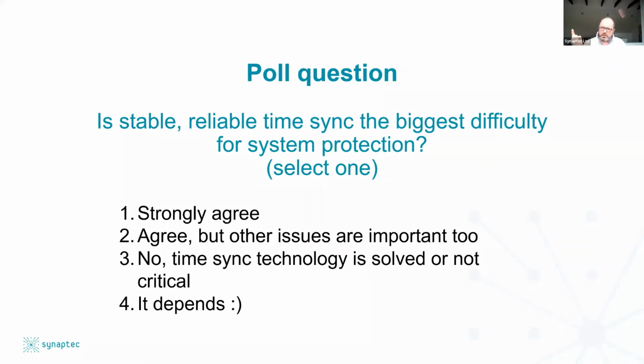So we don't lose relative sync even if there's an outage anywhere in the system. The only thing connecting those remote sensors to and fro, literally, are colors of light, so there is no data outside of the substation and no IP packet switching or latency challenges happening within the system. That's one thing we noticed is very important to the industry: that we can pick up on that and ensure centralized, single-point timestamping and publication of data.